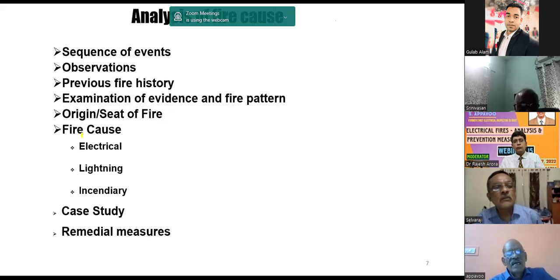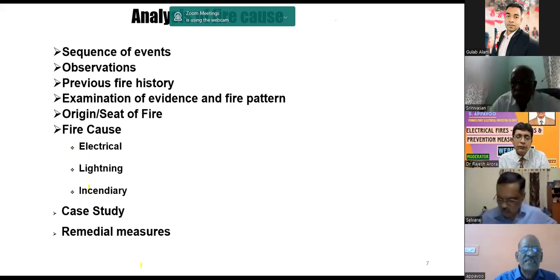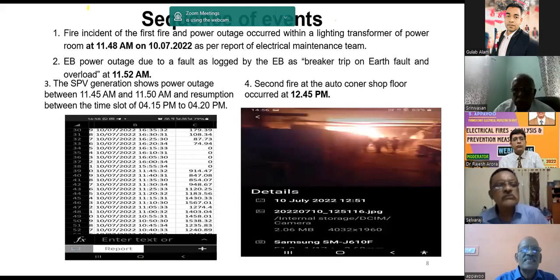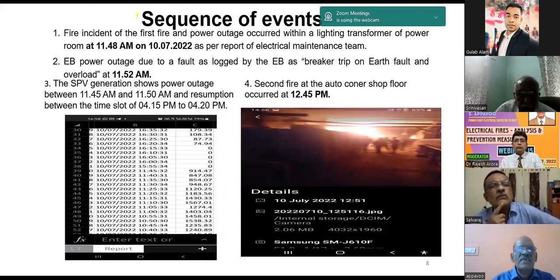Once we know the origin or the seat of fire, then only can we see what fire cause is possible. There are a lot of fire causes possible in a fire, but I am limiting it to these three elements: electrical, lightning, and incendiary, along with a case study. Finally, I will be recommending some remedial measures for the fire cause. When I investigated a typical textile mill fire in Andhra Pradesh, I learned several things. First, I assessed the sequence of events.